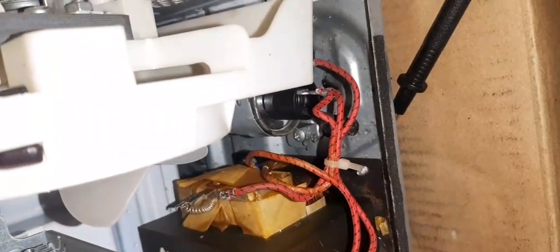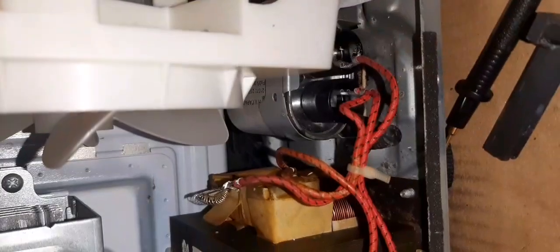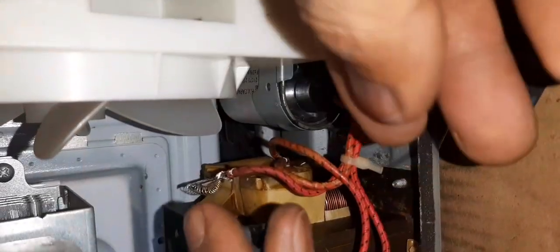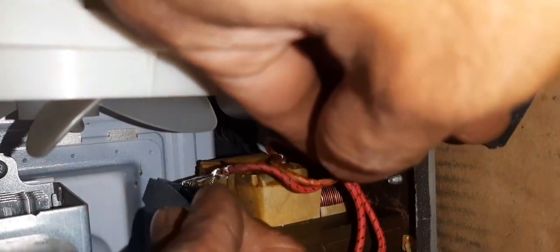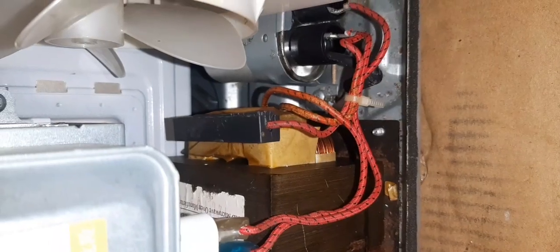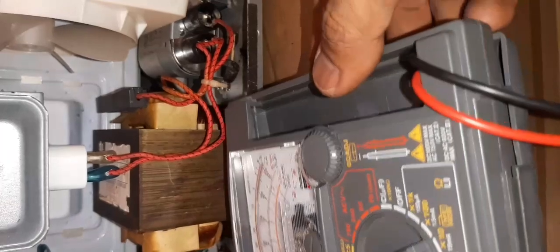Now let's try to reconnect this high voltage fuse and test the running current. Now the high voltage fuse is reconnected, let's put back the fuse holder. Now the fuse holder already holds the fuse. Let's try to measure the resistance of this high voltage winding. It must have 160 to 300 ohms. Once it drops below 160, the winding must have shorted.